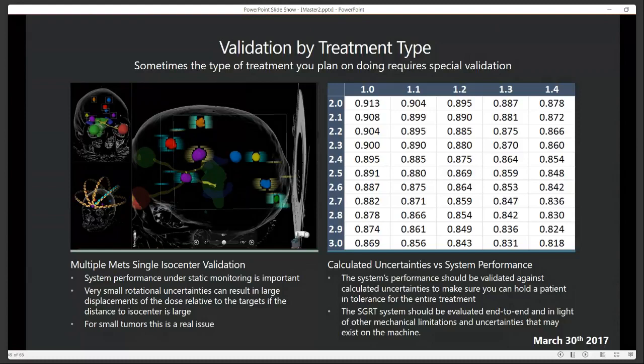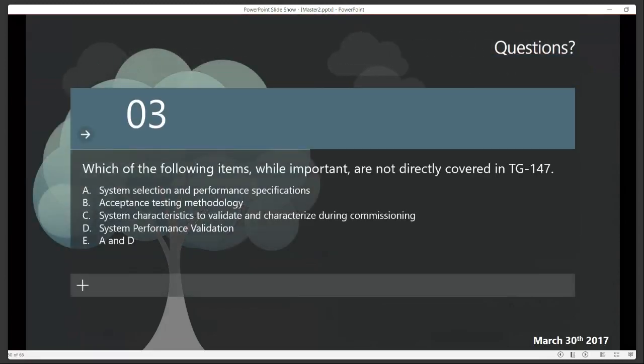And so validating the fact that the system can hold the accuracy and precision over the entire treatment time for these types of treatments can be mathematically verified, but should be verified against actual performance on the system. Not just, well, I can hold it on a phantom, and so everything should be fine. I can treat something that's 12 centimeters away from isocenter with a very high degree of fidelity. That's not necessarily the case. And so with that, we're going to have another question.